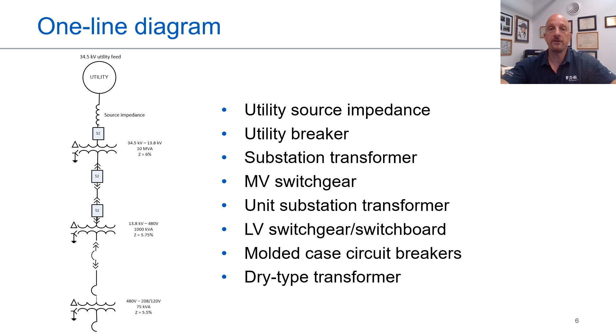But if we have the one line, like in this case, we can calculate and we can use the utility source impedance, the utility main breaker, substation transformer, medium voltage switchgear, like we show in the middle, unit substation transformer, for example, and then low voltage switchgear or switchboards, then molded case breakers and dry type transformers down through the system. So all of that equipment with its proper information on the one line is going to be super helpful to doing your fault analysis and your load flow calculations and all of the things you'll do as an engineer or consultant.